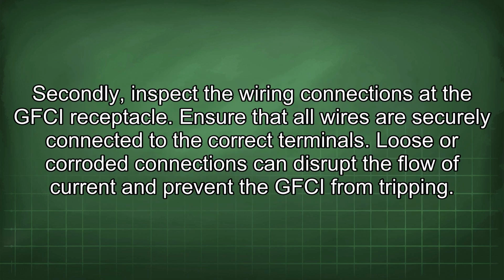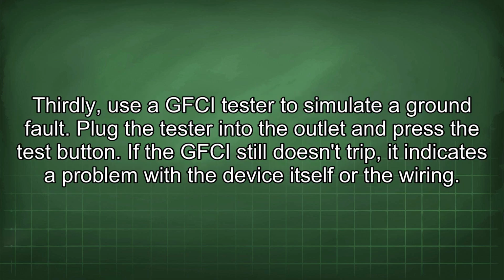The resistance should be very low, ideally close to 0 ohms. Secondly, inspect the wiring connections at the GFCI receptacle. Ensure that all wires are securely connected to the correct terminals. Loose or corroded connections can disrupt the flow of current and prevent the GFCI from tripping. Thirdly, use a GFCI tester to simulate the ground fault. Plug the tester into the outlet and press the test button. If the GFCI still doesn't trip, it indicates a problem with the device itself or the wiring.